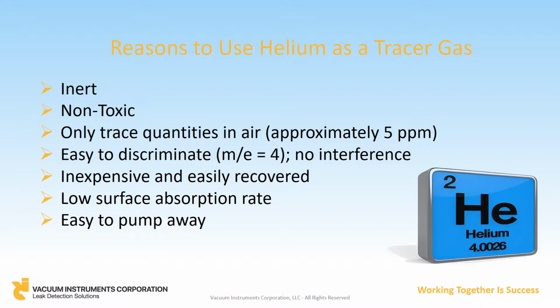Helium is by far the most popular tracer gas used in today's leak testing arena. The gas was first used for leak detection during the Manhattan Project as a means of verifying vacuum process. Today, helium is used to test the leak integrity for many products in both commercial and consumer industries. The reasons why become obvious when you consider the following. It's one of only a few noble gases. These elements are totally inert and non-toxic. Its concentration in our environment is very low, at approximately 5 ppm, or parts per million. And finally, it can be easily resolved from the other elements using a mass spectrometer instrument.